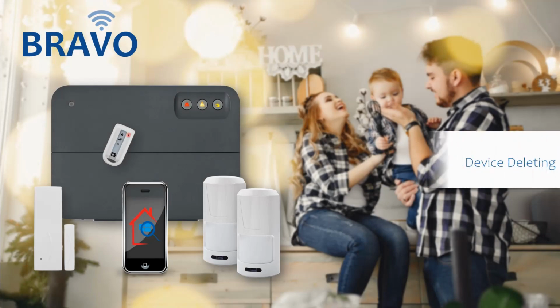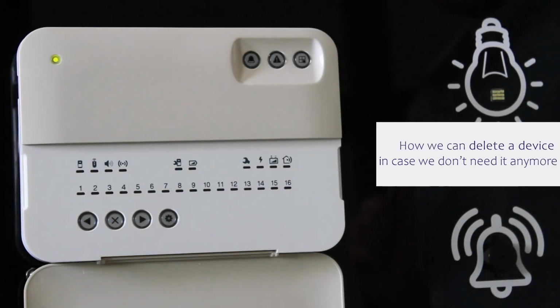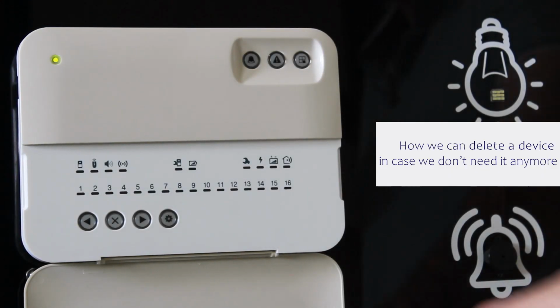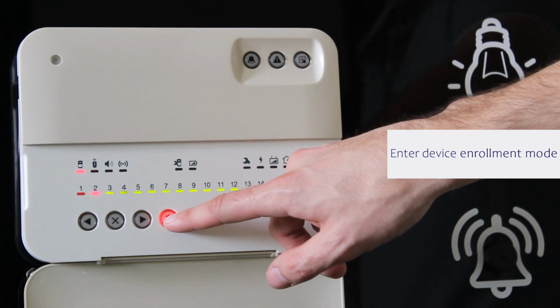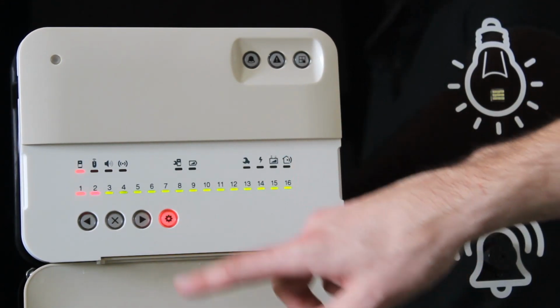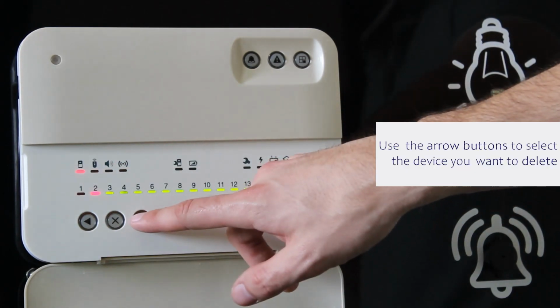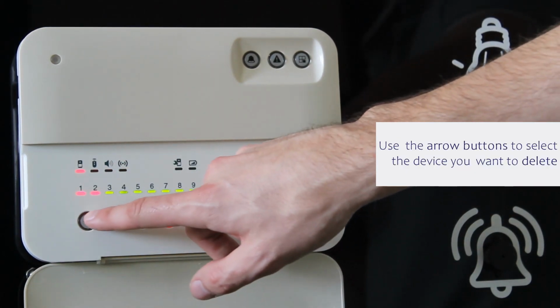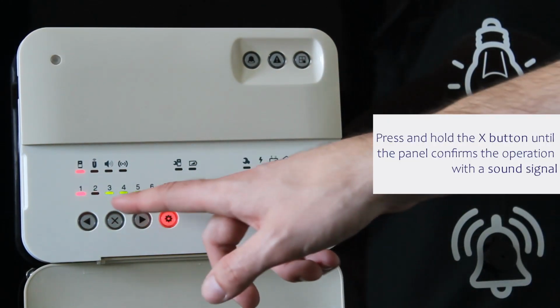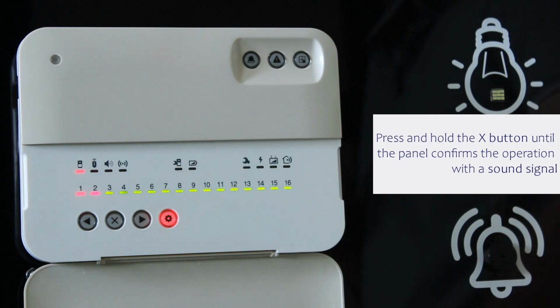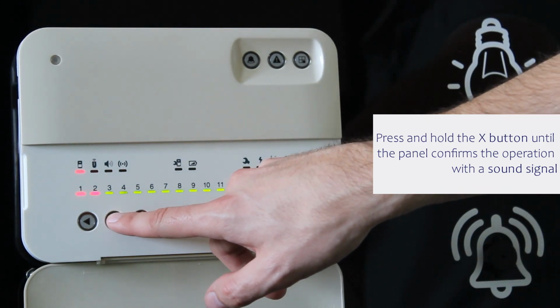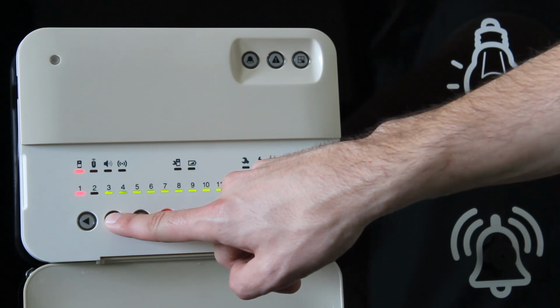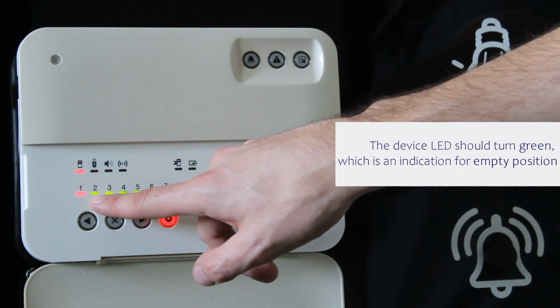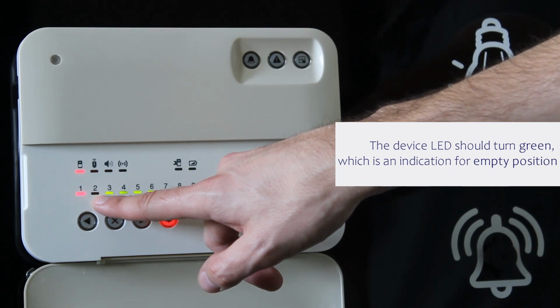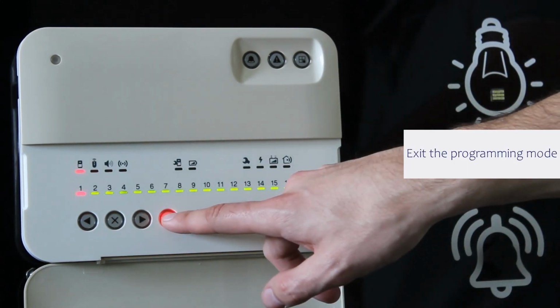We already know how to disable devices, but here's how we can delete a device in case we don't need it anymore. We need to enter device enrollment mode again. Then by using the arrow buttons, we can select the device we want to delete. When we select the device, we can press and hold the X button until the panel confirms the operation with a sound signal. The device LED should turn green, which is an indication for empty position. Then we can exit the programming mode.